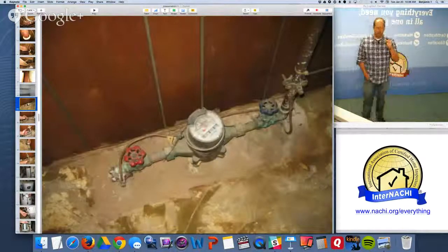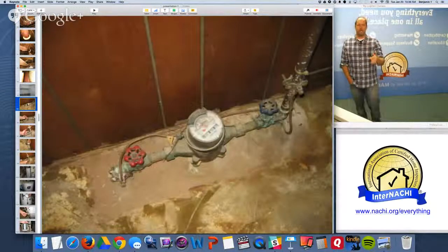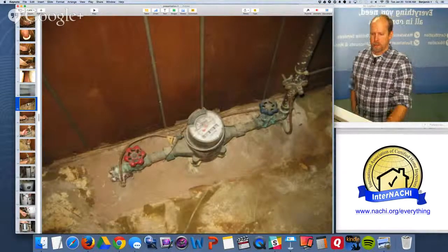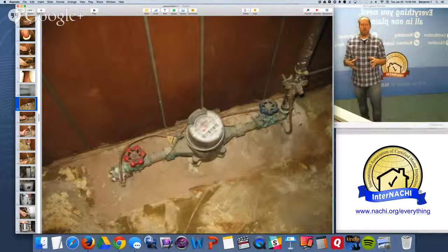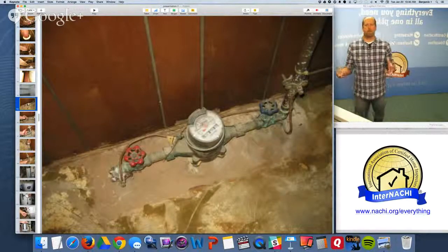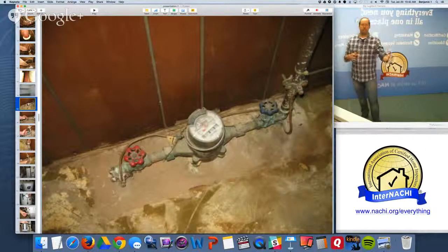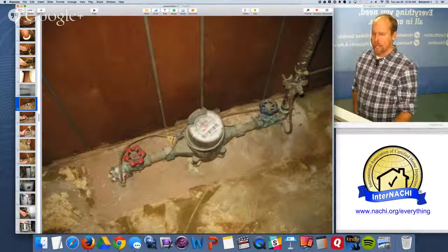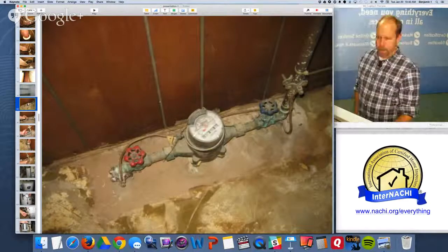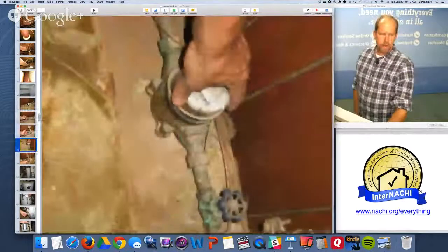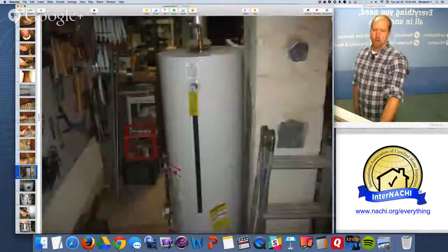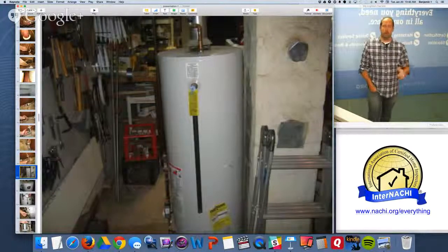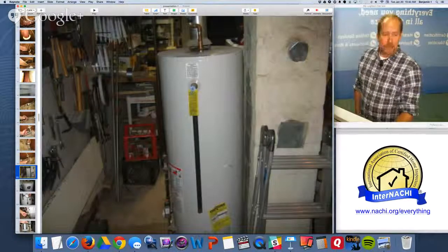Getting back here — there's the water coming in. My sequence is: roof system, exterior, basement, heating, cooling, and now I'm doing water in and drain out. I think of the home as a system of interdependent parts — affect one system and it affects all others. Water comes in from the street underground: shutoff valve, water meter, jumper. Hot water source: I know we have natural gas coming to the house, so the gas is also supplying the hot water source. There it is — it's a natural draft hot water tank. The heating system no longer uses the chimney because it's high efficiency with intake and exhaust pipes outside, so the chimney must be for the hot water tank.